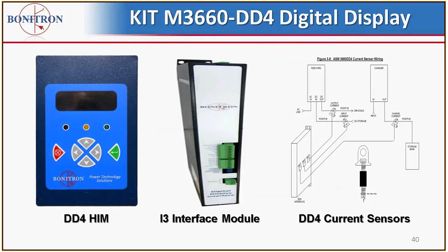We do provide these kits loosely if you're just buying the open chassis units, or if you're just buying the modules for a full outage system. It also includes the i3 interface module, which is standard in the 3534s now. And there's a current sensor network that has to be configured, as you see in the drawing, which goes with the whole kit. This is all included in a separate kit that can be provided with the modules and a remote display cable that can go out to the front end of an already installed cabinet. Let's say the customer may want to use his own cabinet, his drive cabinet has room for the system, so we just need to know the cable length for that.